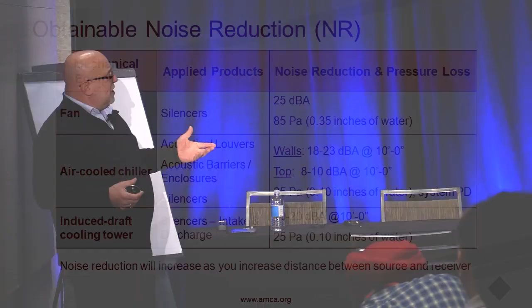But if we put a wall up, and let's say there's an air-cooled chiller in the middle of this room, and we've got a wall all the way around, not this tall, but let's say 10 foot or 12 foot tall, it's realistic to see an 18 to 23 dBA reduction 90 degrees away on the outside of the wall from the equipment. Out the top, there are some things you can do that allow it to breathe properly. Let's say you've got a pit of air-cooled chillers, but you have condos and balconies above it. You can realistically get 8 to 10 dBA reduction at 10 feet above the units, at a total system pressure drop of 1/10 of an inch from the intake to discharge, 1/10 of an inch.